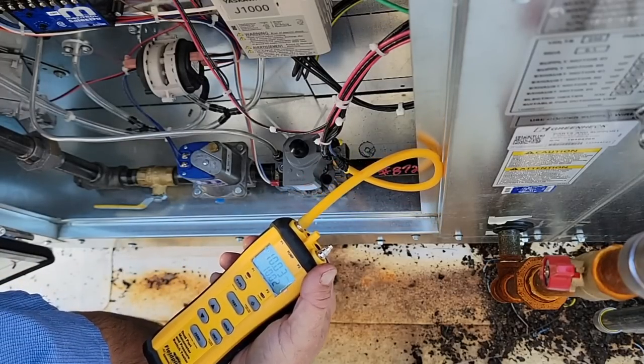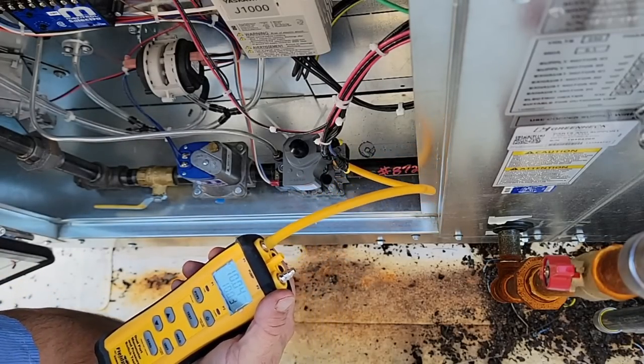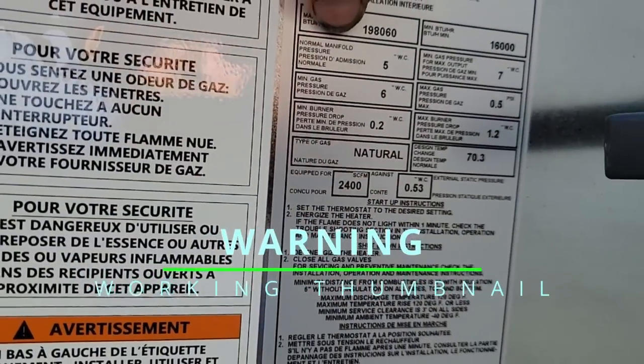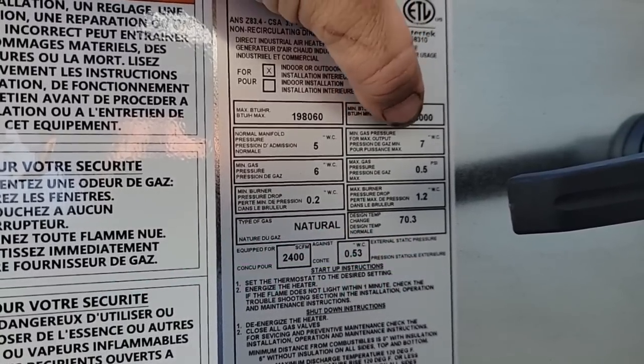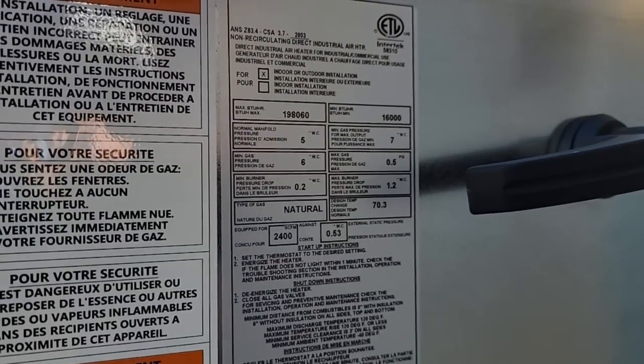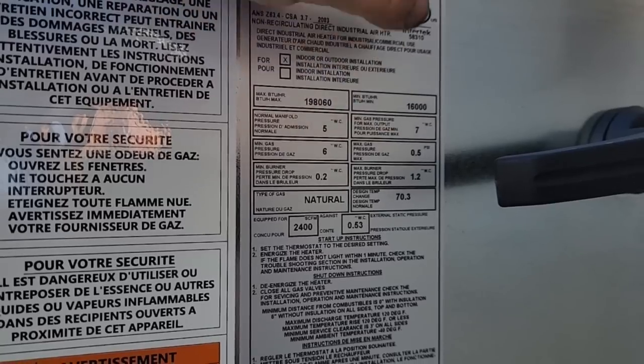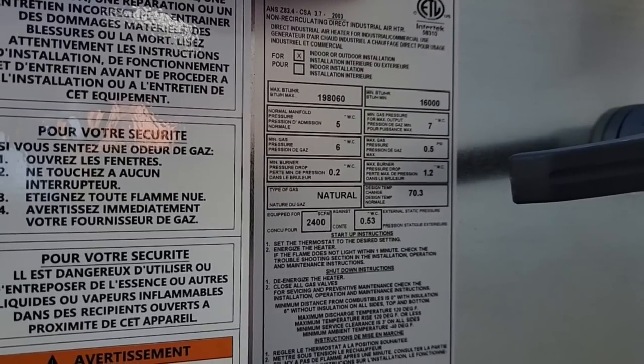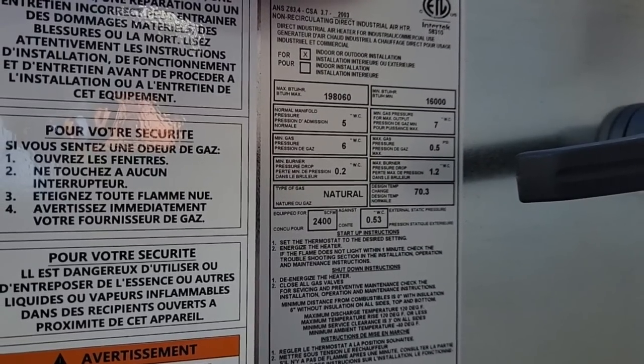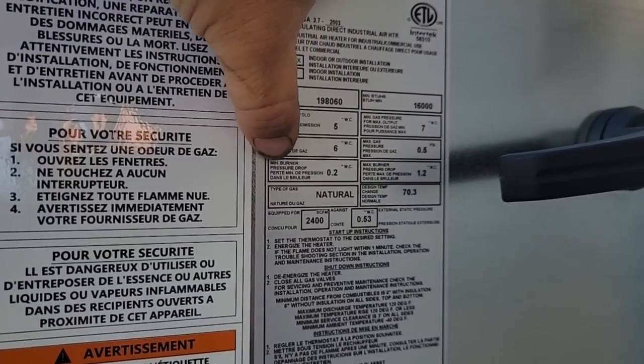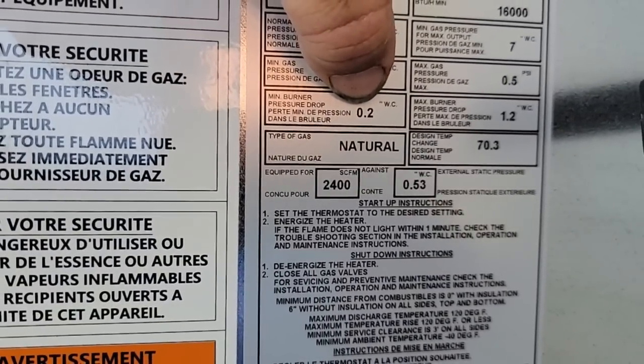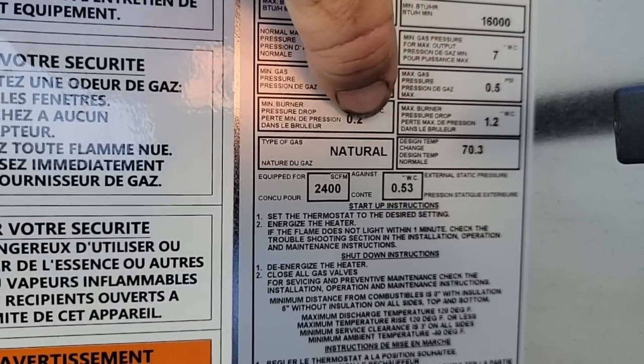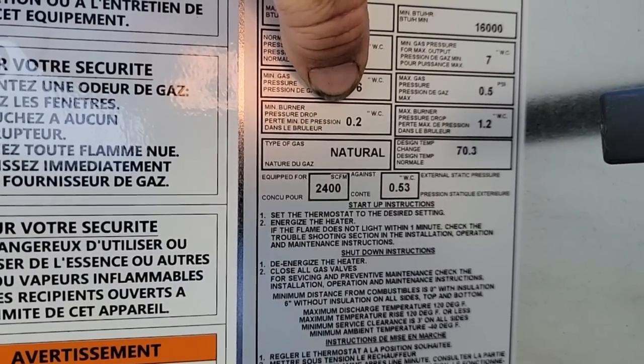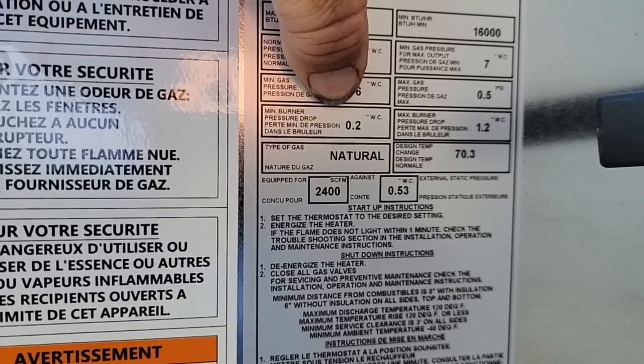Let's take a look here at our data plate somewhere in here. It should have it. Normal manifold pressure, 5 inches. Minimum gas pressure for maximum output, 7 inches. They don't really read it as a maximum, but we're gonna be fine. We definitely hit our minimum. Usually 13 inches is where things start getting crappy. And there is our pressure drop right at those two marks right there. We need to be between 0.2 and 1.2 for our plate adjustments on our differential, which I'll shoot, I think, for 0.6.